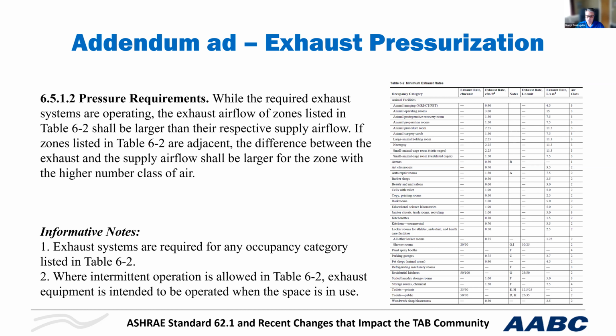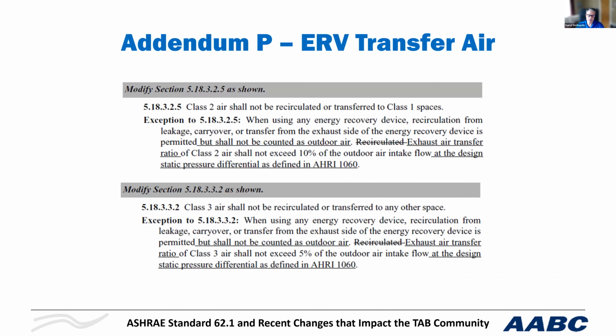So you see on hospital drawings, you see on laboratory drawings, you see pressure and flow diagrams. I'm a proponent of seeing these on all mechanical systems, because you have to understand the buildings are very complex. The building itself is a living system. You're going to have stack pressure. You're going to have doors opening and closing. You're going to have mechanical systems with variable speed. So there's a lot of dynamics going on. And if you have flow diagrams showing what's happening, then you have a better chance of making sure it happens in reality.